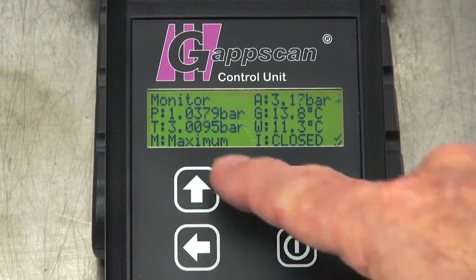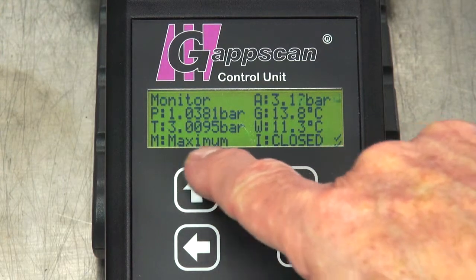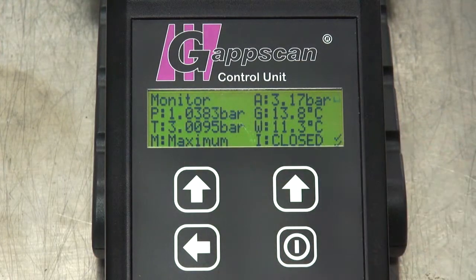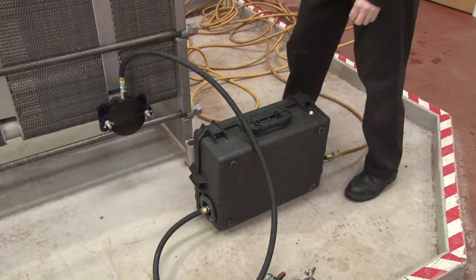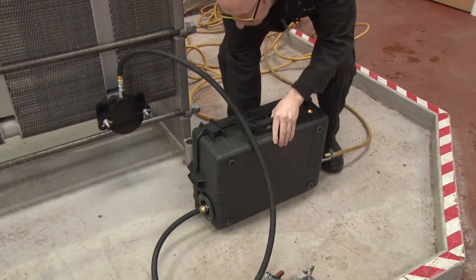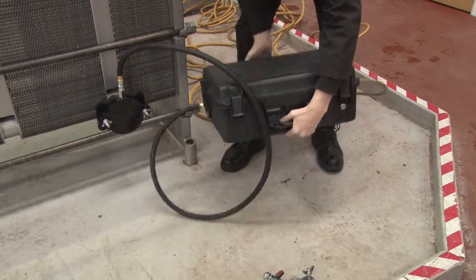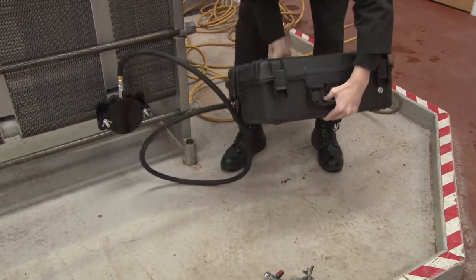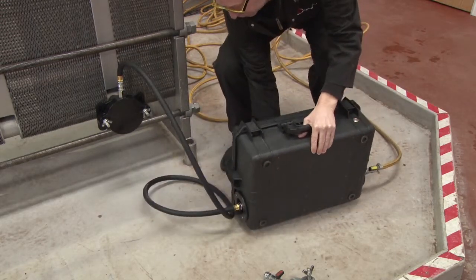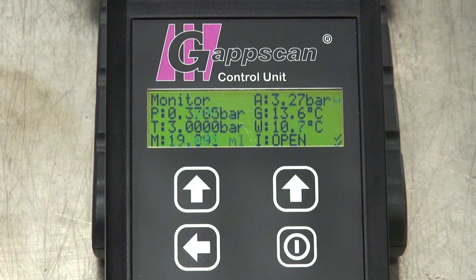If, when in monitor mode, you see maximum displayed at M, the measured flow, it means there is an airlock in the Gappscan unit. To remove this, simply turn the unit upside down as shown here. The unit will make this sound and maximum should disappear from the control unit.